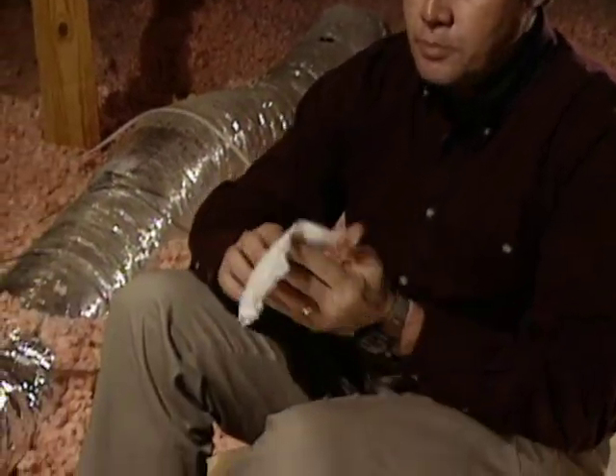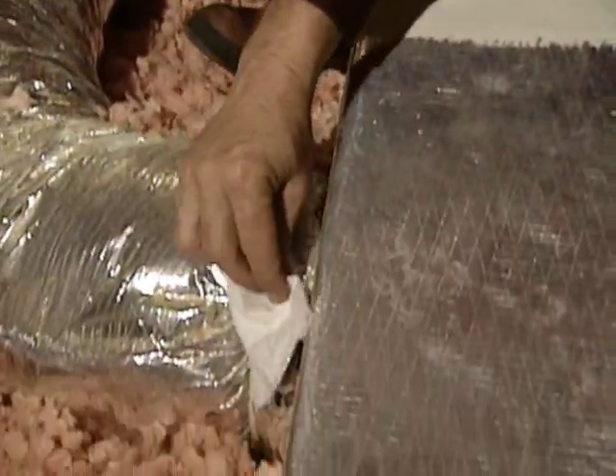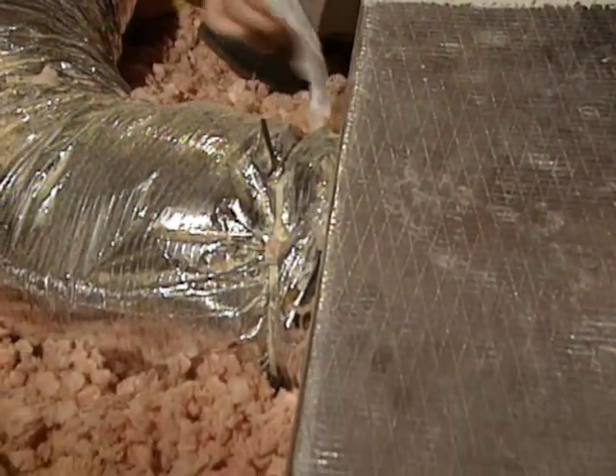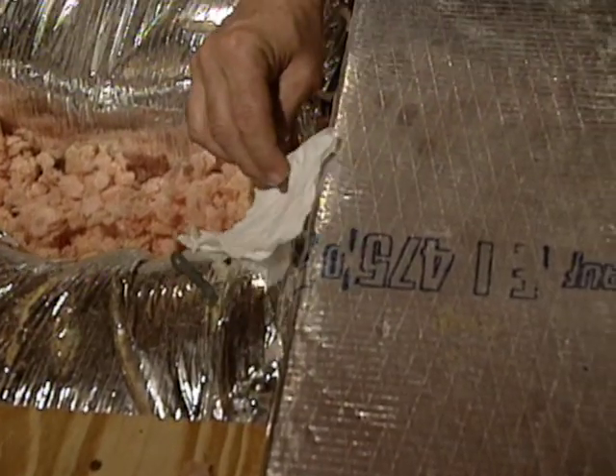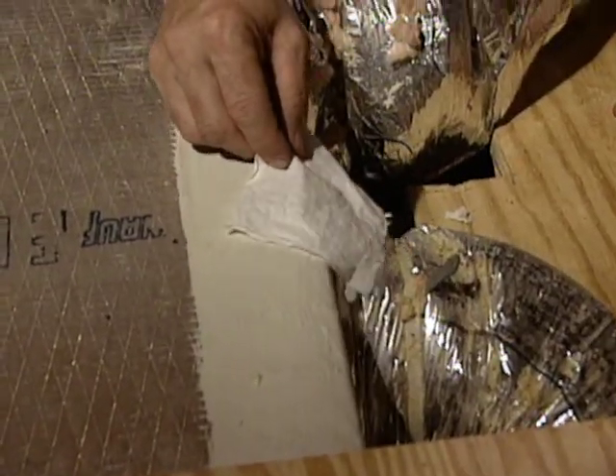To test that, turn your unit on and just take a simple tissue and go along anywhere that the ductwork may tie into this, and if there's any leak at all, you'll see it in the movement of the tissue. Now, obviously, the homeowners here have had some duct repair done at some point recently because of the presence of the duct mastic.